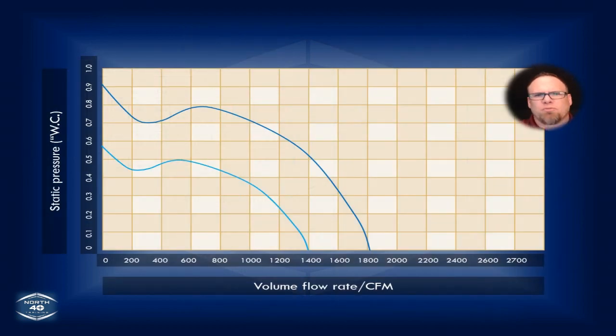So looking at a blower performance chart, this is another version of the blower performance chart in which you see what's called a fan curve. Those two weird lines in all the checkers there are telling you where that fan is operating as far as CFM goes and static goes throughout the cycle of that fan operating. Okay, so if you look across the bottom, you see the CFMs. Okay, that is airflow in CFMs.